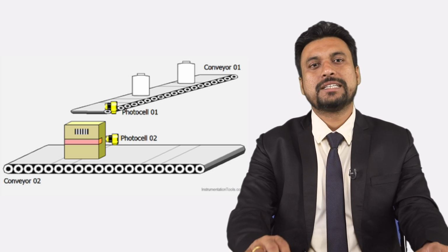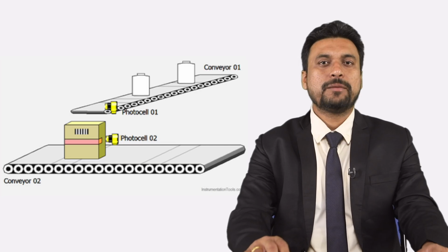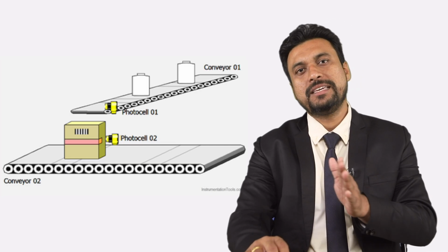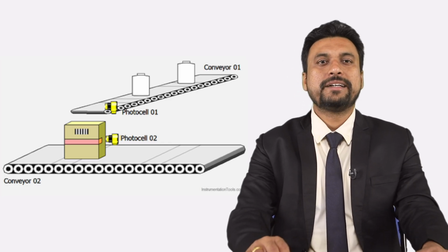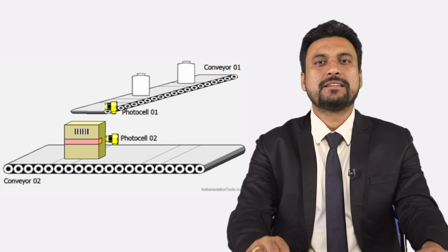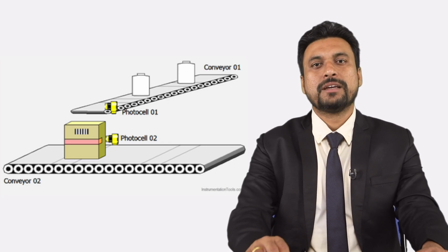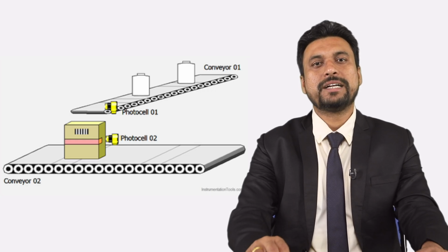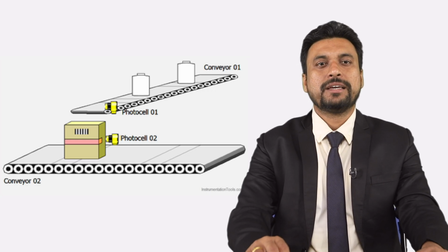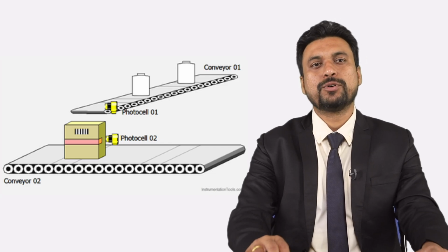For this, just take a quick recap of the up counter and the down counter. In up counters, we get the done bit high when the accumulator value is equal to the preset value. But in the case of down counters, we get the done bit high when the accumulator is greater than the preset value, because the down counter counts in decreasing order, and the done bit goes low when the accumulator is less than the preset value, as I just explained 5 minutes before.